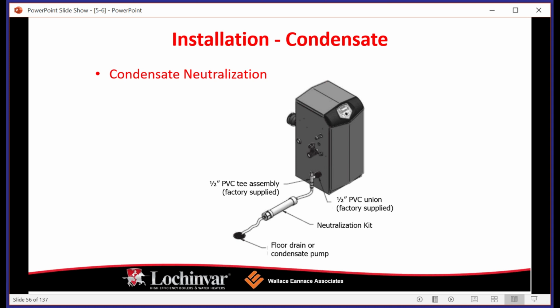So for example, if you've ever seen anybody who tried to pipe the condensing water through copper, it'll eat through copper in a very short amount of time. It'll turn your copper pipe into a canoe in no time. So again, best practice is important. You want to use PVC, right? You're going to use a plastic which is not subject to the acidity in the water, and you're going to capture that condensate through the trap.